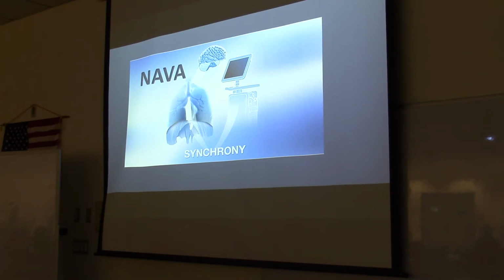movement of the diaphragm. So the signal from the phrenic nerve to the diaphragm can be picked up with this tube that's in the esophagus. And from that, you can see when the diaphragm is getting ready to contract, because there's going to be an increase in the electrical impulse. The diaphragm's getting ready to contract. So when you take that information and feed it into the ventilator, it can synchronize the brain's signal to tell the diaphragm to contract with when the breath is delivered to the patient.